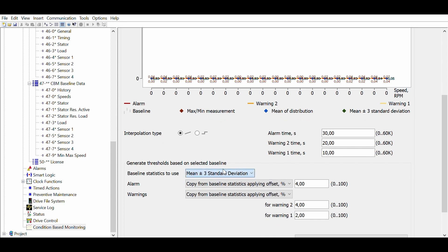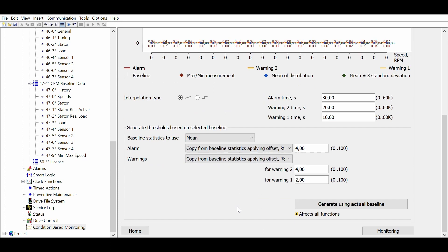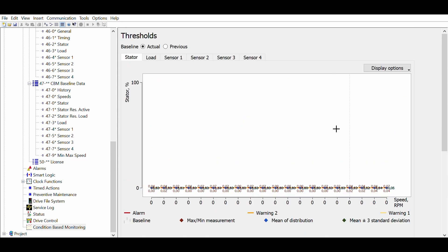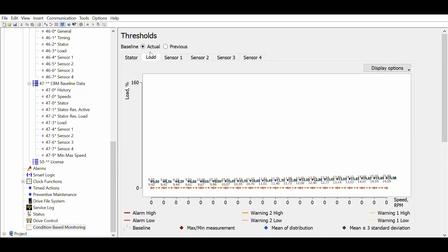The baseline measurement is a complete statistical model. You can select whether you will base the threshold on the mean baseline values, on the mean plus 3 standard deviation, or on the max min values. For the winding monitoring, just use the default settings for the threshold levels.